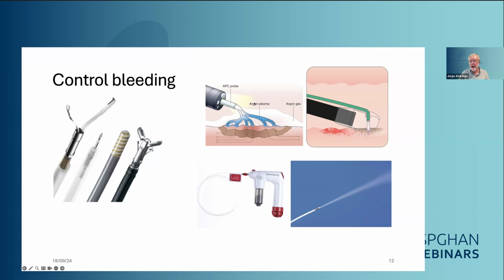Another recent advance is argon plasma. Argon plasma is deployed through a catheter without actually touching the mucosa, and this electric current and the gas will coagulate the mucosa. And depending on the definition of the current, you define how deep you want to address the coagulation. There is also an auxiliary device which uses this trick applied to the tip of the endoscope, and this is the cannula for the argon plasma. And by using this, you can have a good view and apply it at 90 degrees onto the mucosa without obscuring your view. So it is an advance to this one, but the principle is the same.